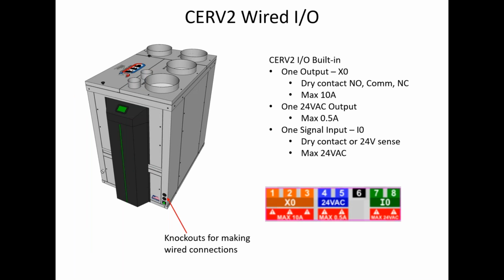The wired inputs built into the unit: there's one output channel. It's either dry contact or 24-volt output. And then there's one input channel built in as well. So that's dry contact or 24-volt sense. So it's a flexible standard communication to the outside.